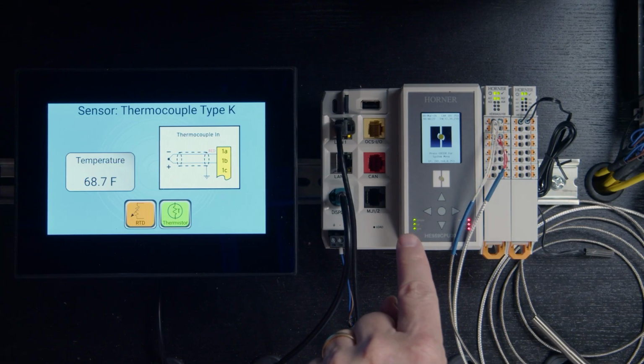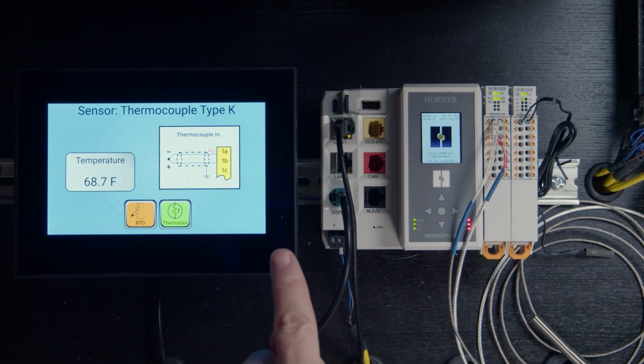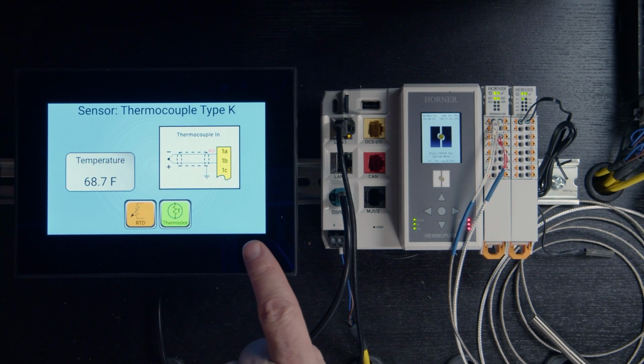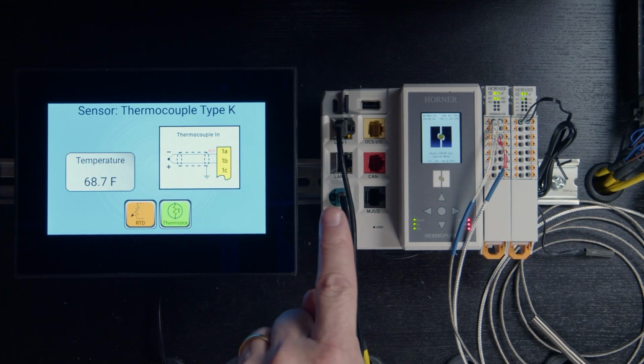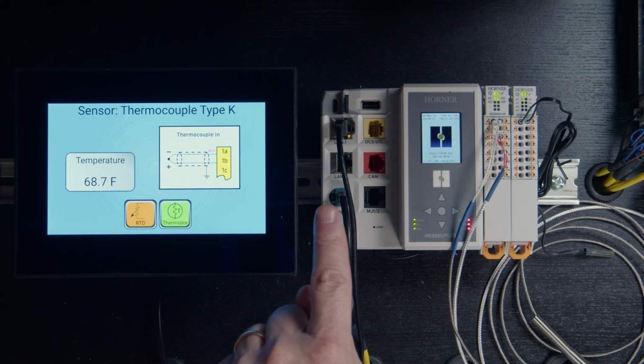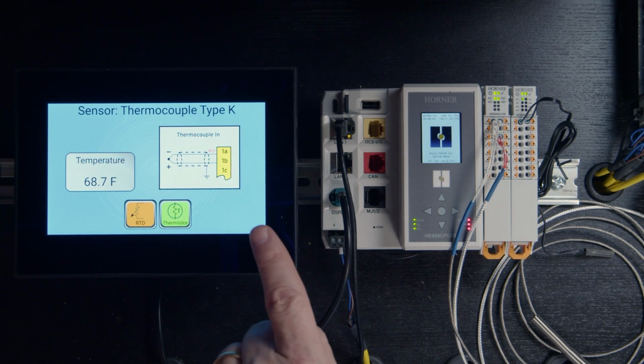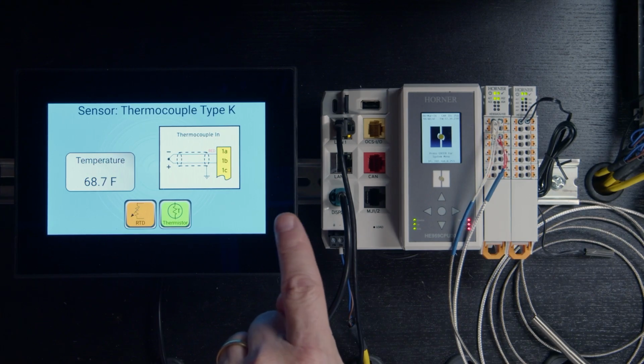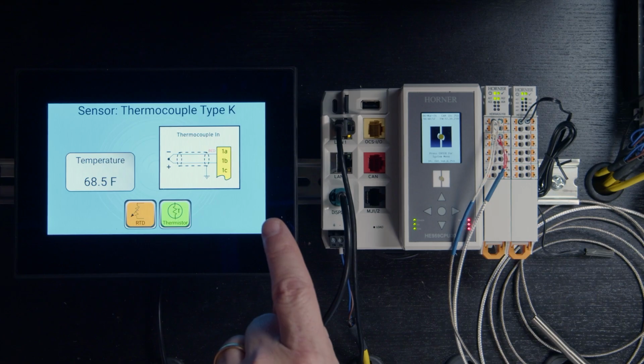The one big difference is that not only does it solve all the logic for the system, but it also handles all the graphics as well. And then the touchscreen is one of our HMI Connect touchscreens, and it's literally just a touchscreen component connected, making an electrical connection here, the same type that's used in your automobile between the touchscreens on your dash and the electronics that control them. So this is a pretty high-tech approach, but the beauty of it is if you ever need to swap out touchscreens, you can do that easily, or if you want to locate the touchscreen pretty much anywhere outside of the panel where the PLC is mounted, that's easy to do as well.